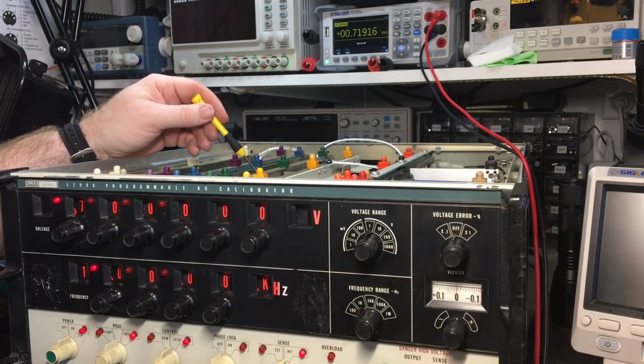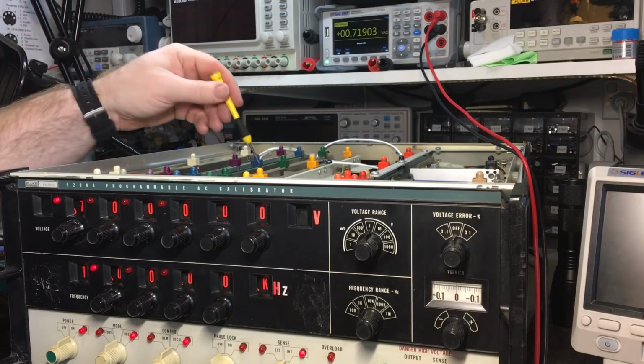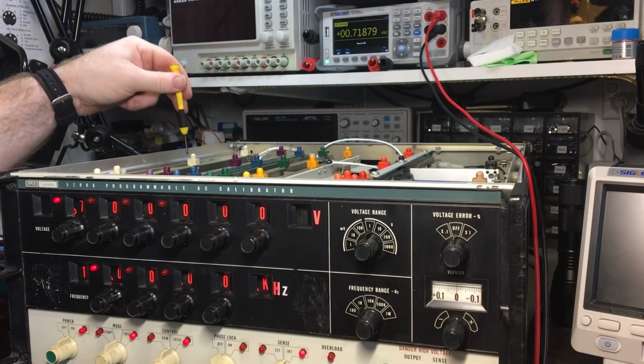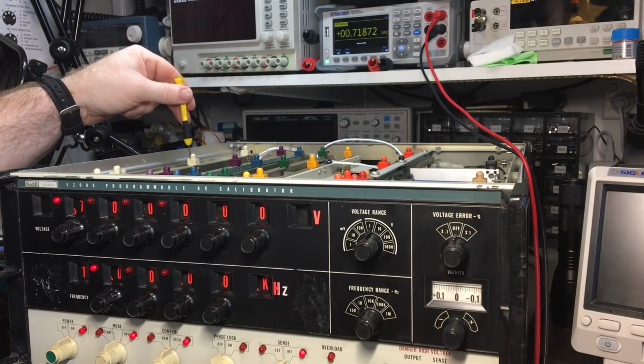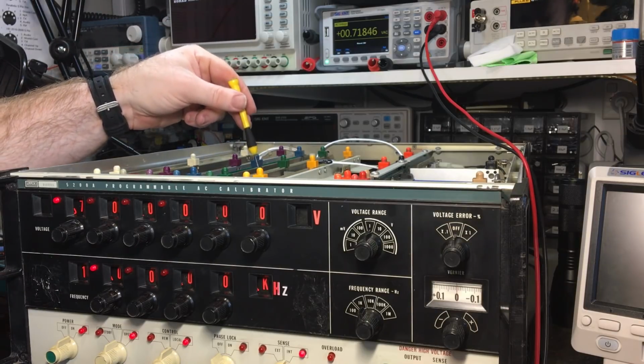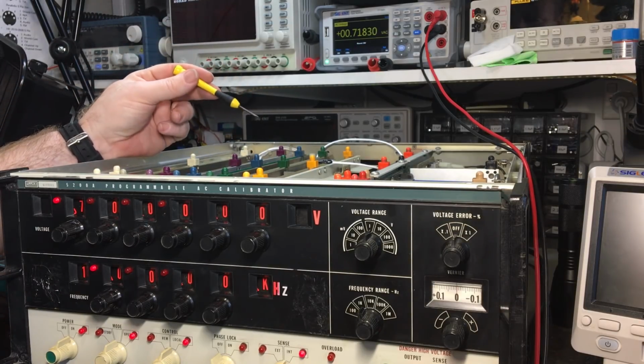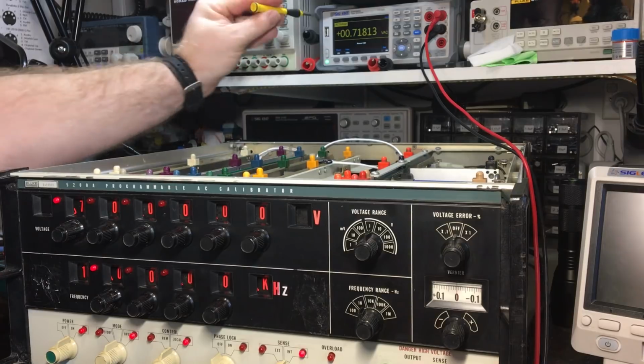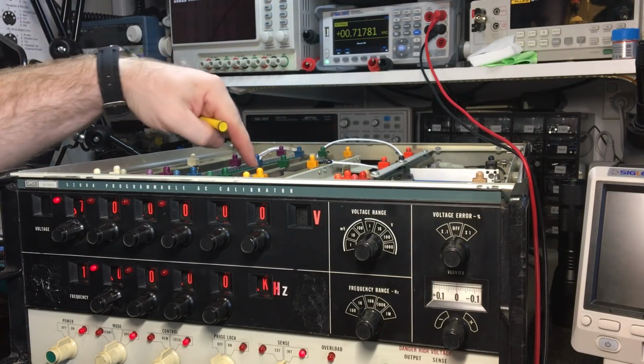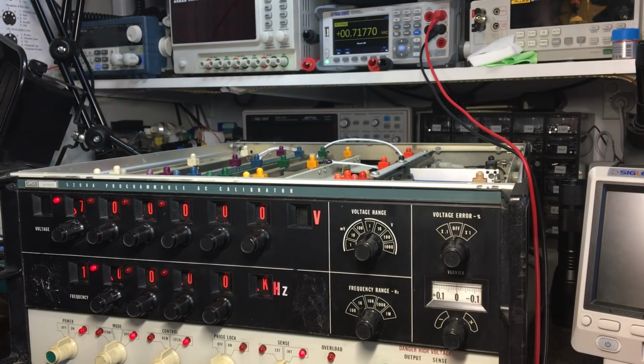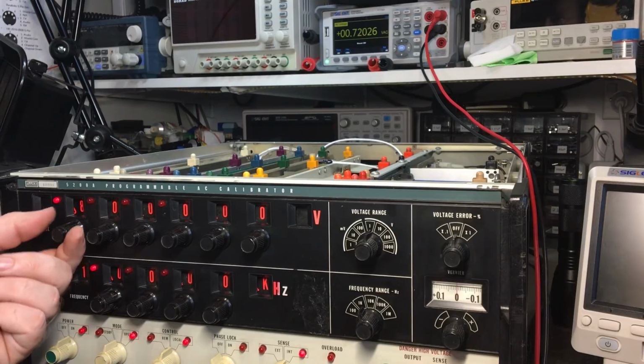So I believe I've still got an issue here with this cable here. You see, from the reference, not being able to drive the correct load, or this is being overloaded in this end somehow. And I think that's why I can't get the correct voltage on here, because it just can't drive enough voltage into the AC card as a reference. Without the correct reference voltage, it can't adjust the output correctly. I think it's got the incorrect output voltage. I have to measure it and confirm that, but it does actually step up now.